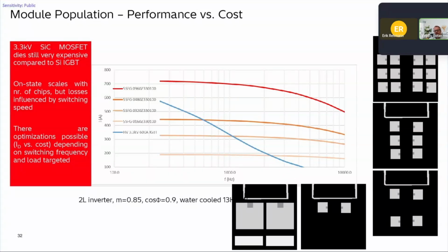That is why the question always arises: if I want to use a silicon carbide device, what is the price against a silicon module? And I always have to say, there's no universal answer, because it depends on the application. If you want to fully populate it with silicon carbide, of course the price difference is quite high. But most likely you don't need to do that because if you want to switch at 2, 3, 5, 8 kilohertz and you have a certain current, maybe even 2 small chips above 3 kilohertz will give you a higher current output than a fully populated silicon. Then when we compare these two, we have a different cost ratio than when comparing the fully populated device.